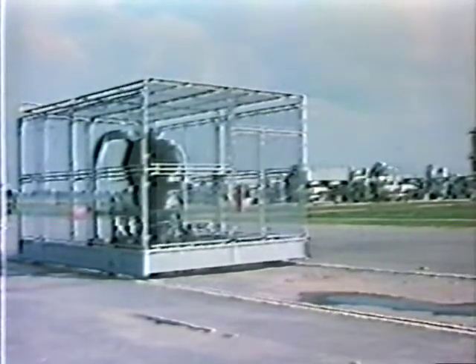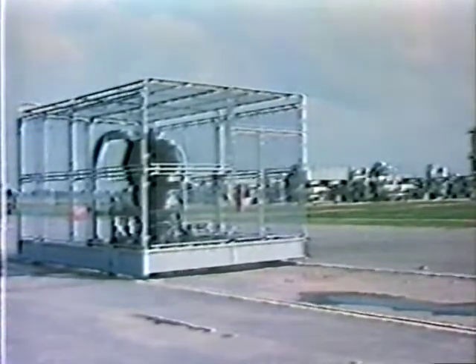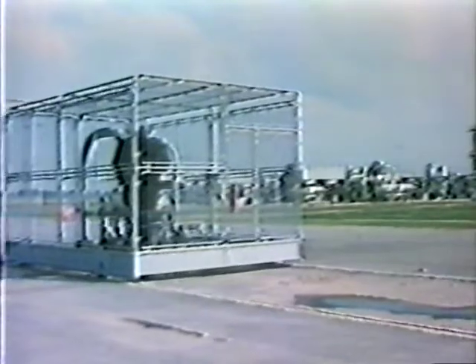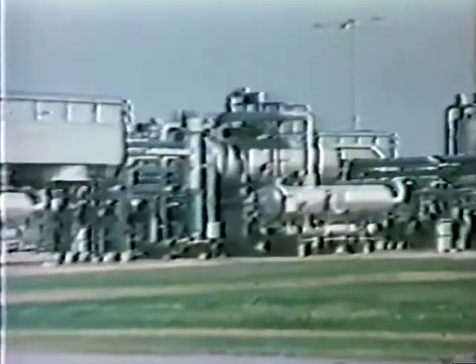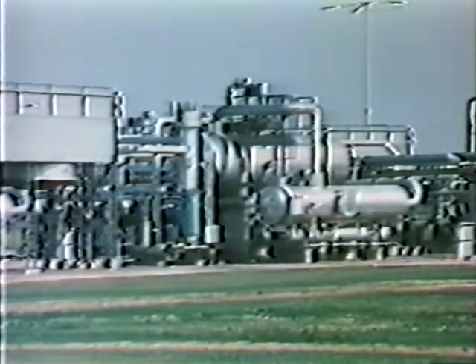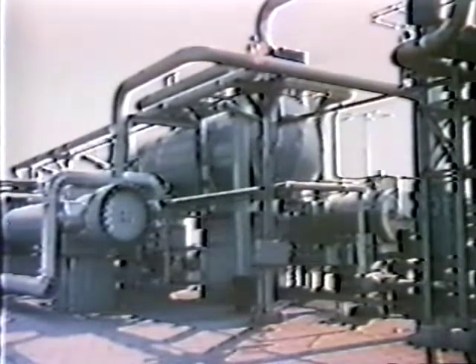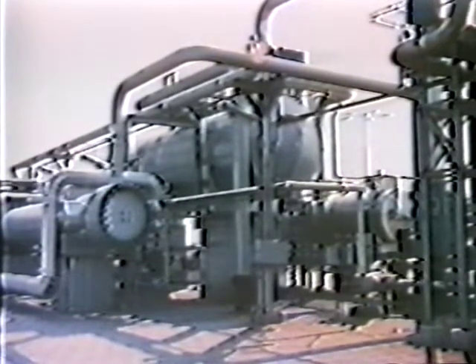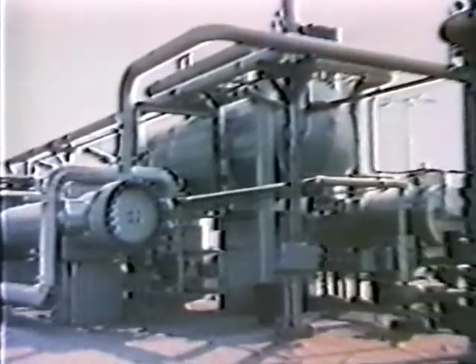At the Groningen gas field, the natural gas produced is freed from undesirable constituents such as sand and liquids. After this, the gas is dried. The drying is necessary to avoid condensation of the heavier hydrocarbons during transport through the pipeline network. In the drying process, use is made of the cooling which occurs when the gas expands from wellhead pressure, here about 200 bar to 74 bar.